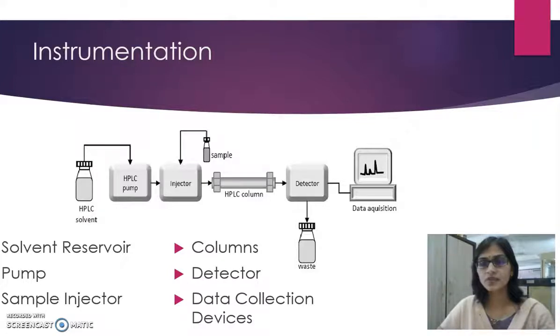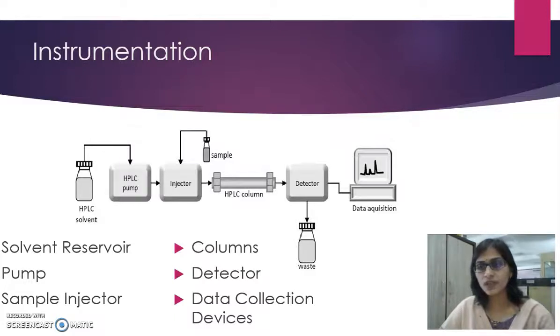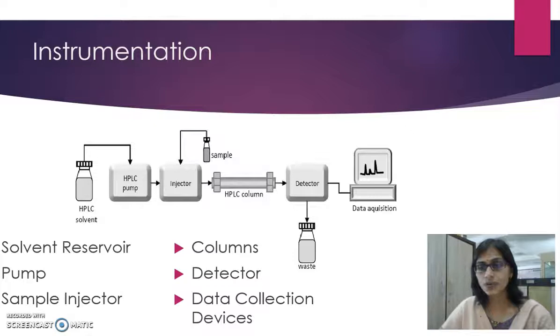Columns with internal diameters of less than 2 mm are often referred to as micro-bore columns. The HPLC detector, located at the end of the column, detects the analytes as they elute from the chromatographic column. Commonly used detectors are UV spectroscopy, fluorescence, photodiode array detectors and electrochemical detectors. For data collection, generally a computer is used; the computer integrates the response of the detector to each component and places it into a chromatograph that is easy to read and interpret.